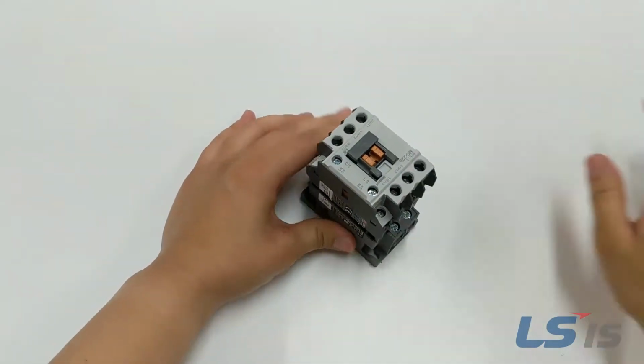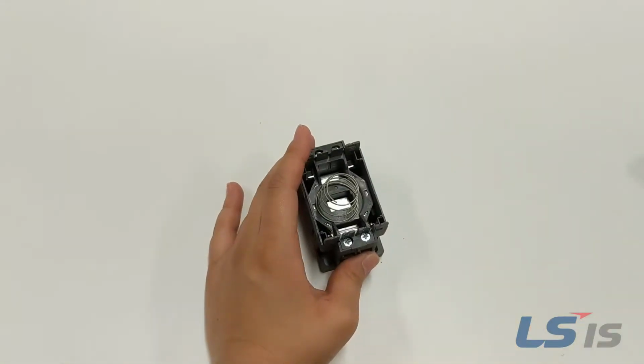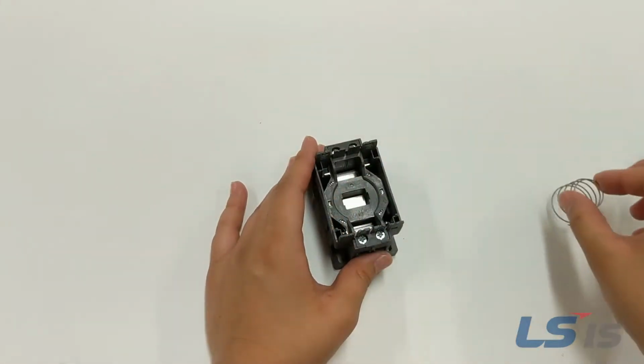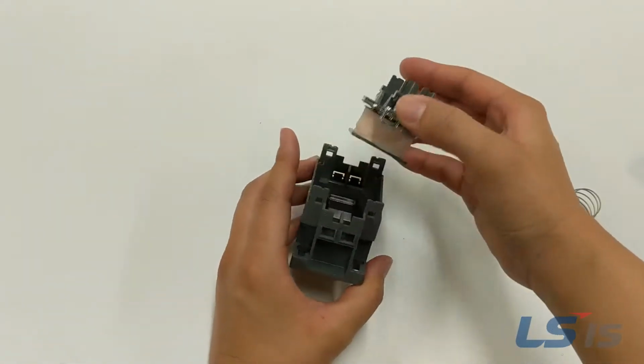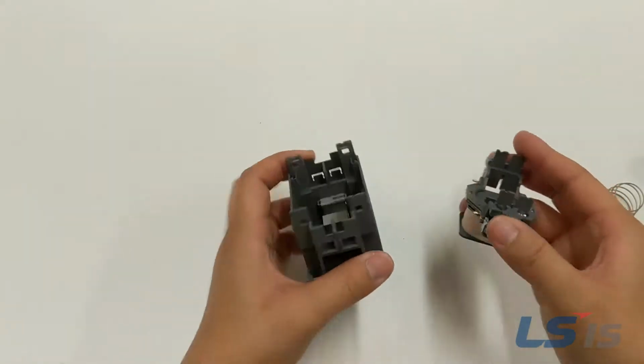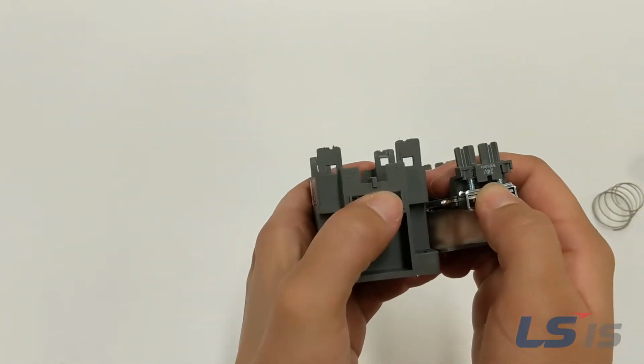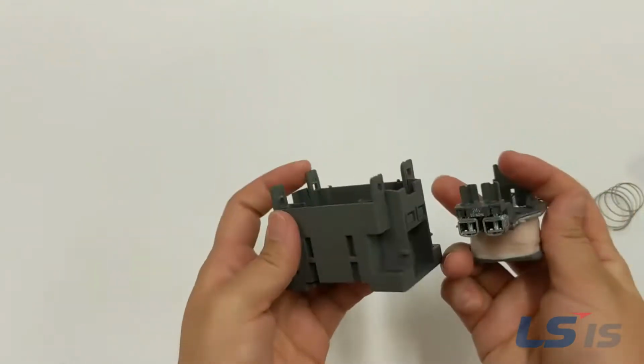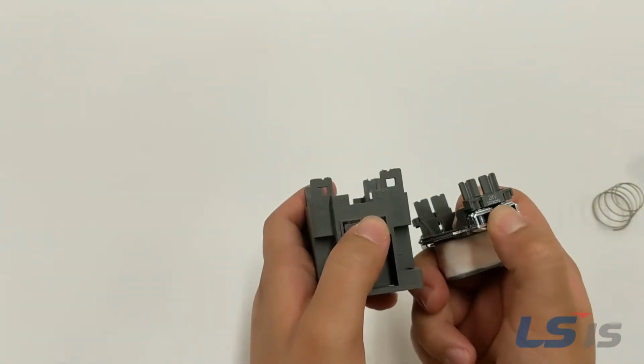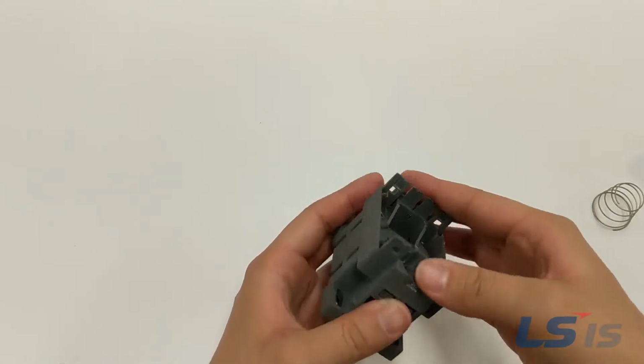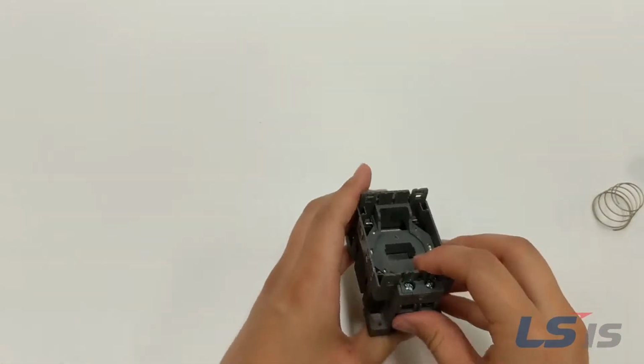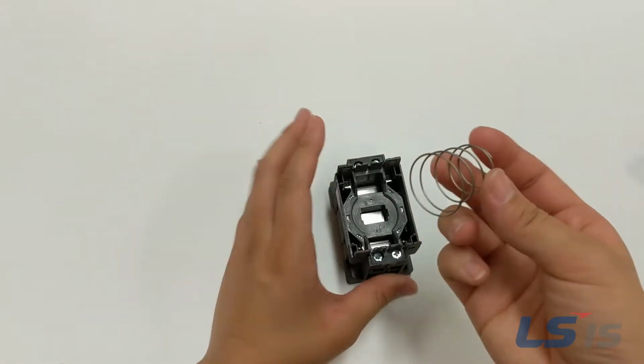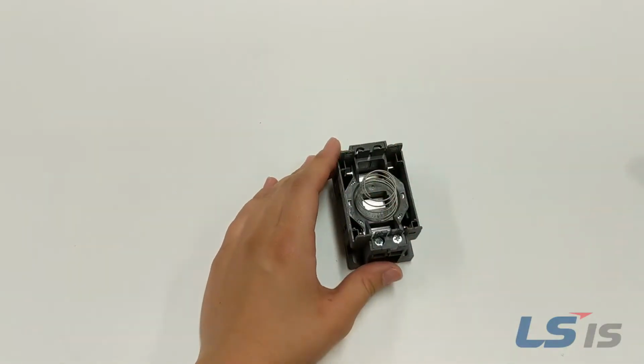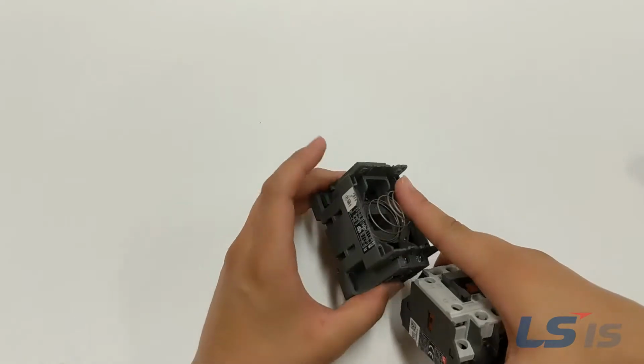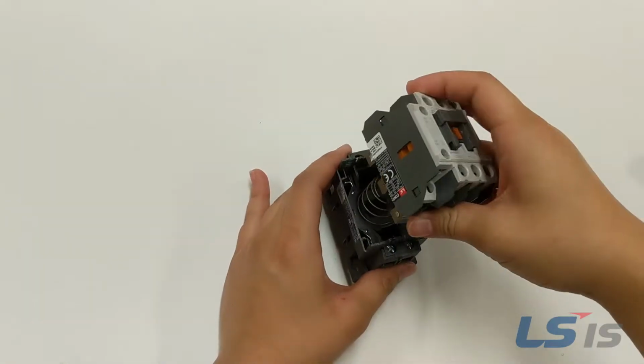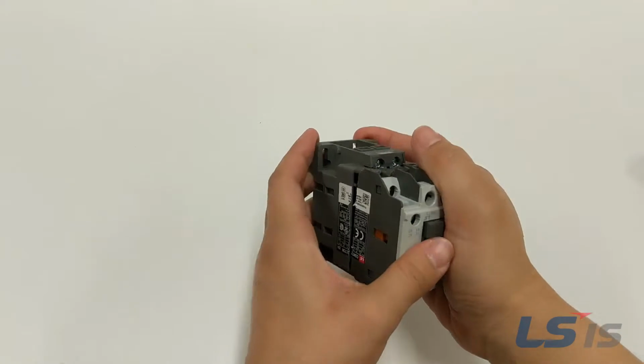Then remove the top half and the spring, and then we can lift the coil out and slide in the replacement coil. Make sure that the notch on the bottom half aligns with the side with the indent so that the coil is placed with the right orientation. Replace the spring with the larger side down and place the top half of the contactor back onto the bottom half to reassemble. Use the nameplate label to confirm the orientation of the top and bottom match and snap together.